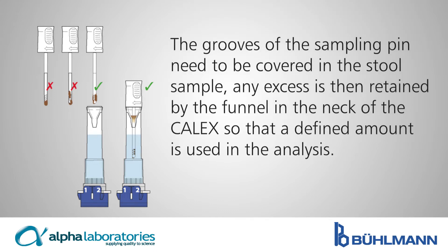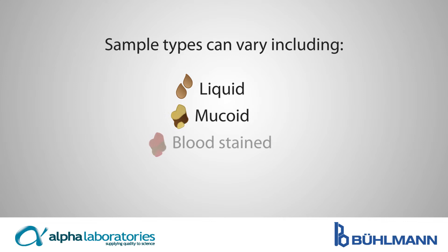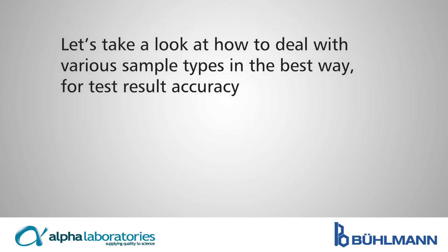The grooves of the sampling pin need to be covered in the stool sample. Any excess is then retained by the funnel in the neck of the CALEX so that a defined amount is used in the analysis. Sample types can vary, including liquid, mucoid, blood-stained, and hard. Let's take a look at how to deal with various sample types in the best way for test accuracy.